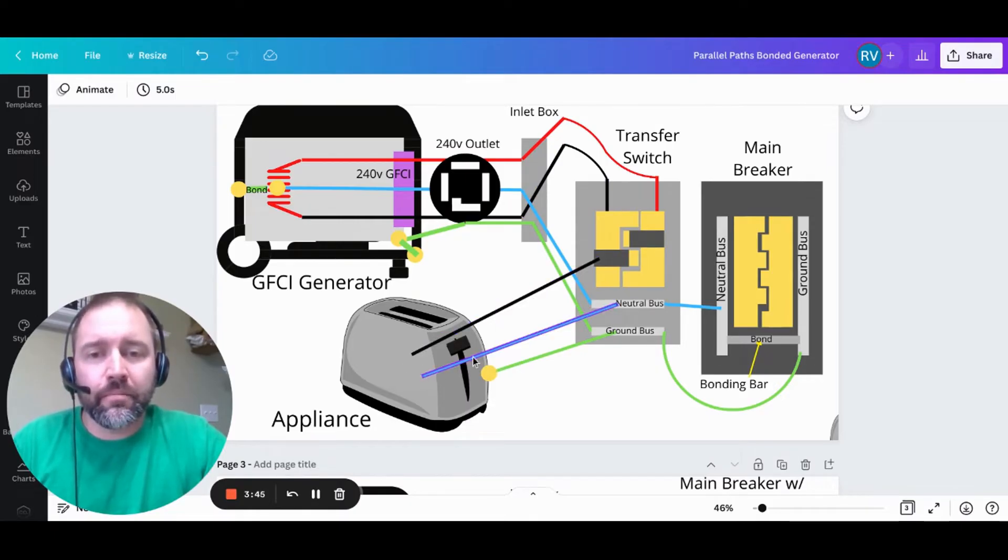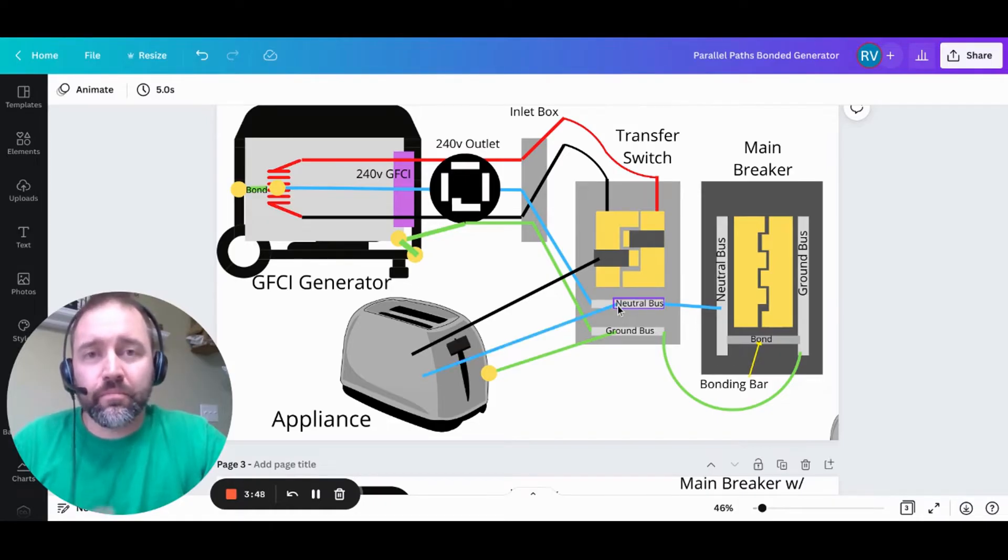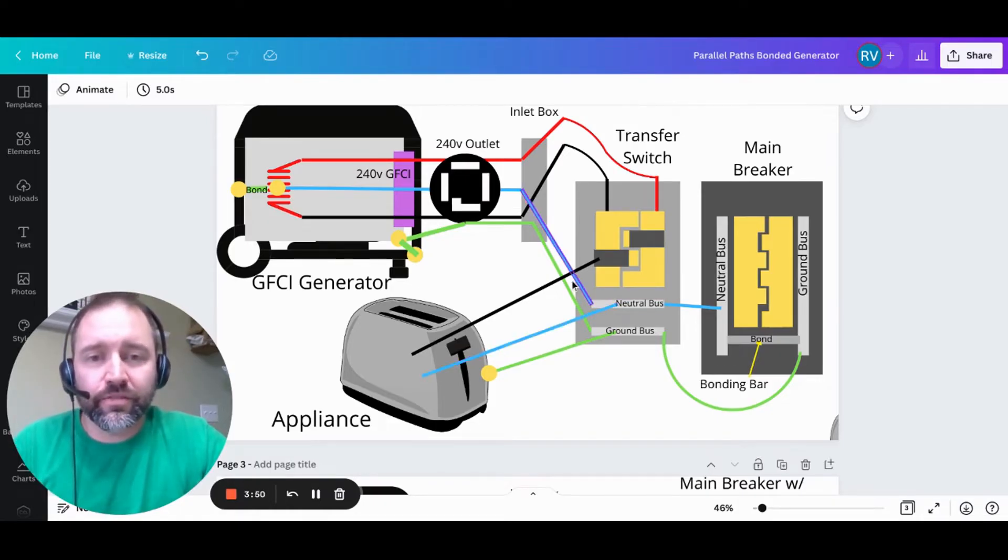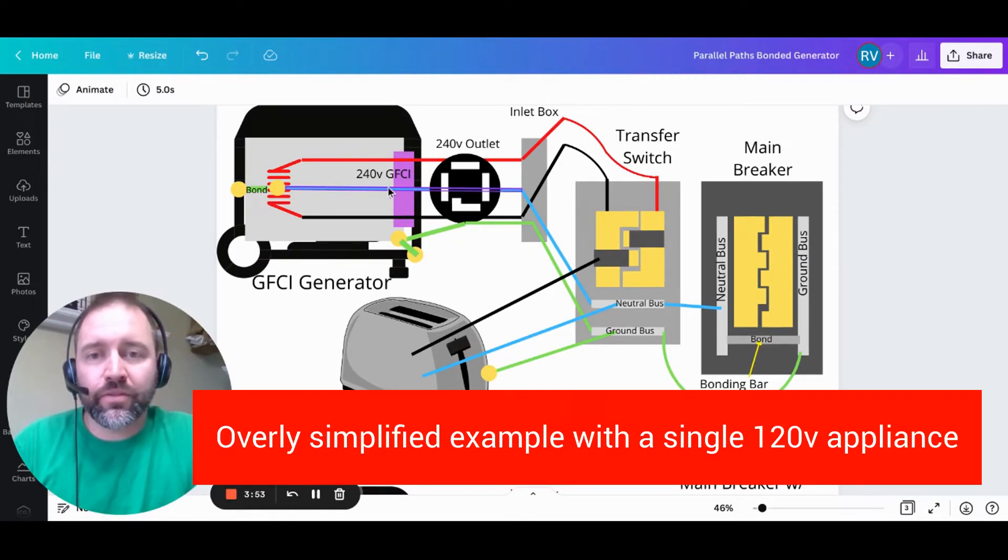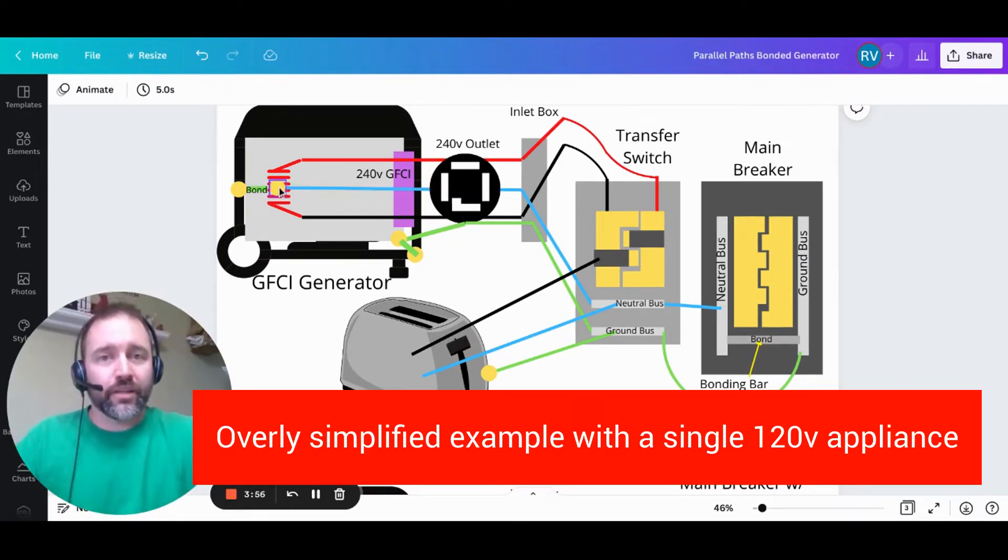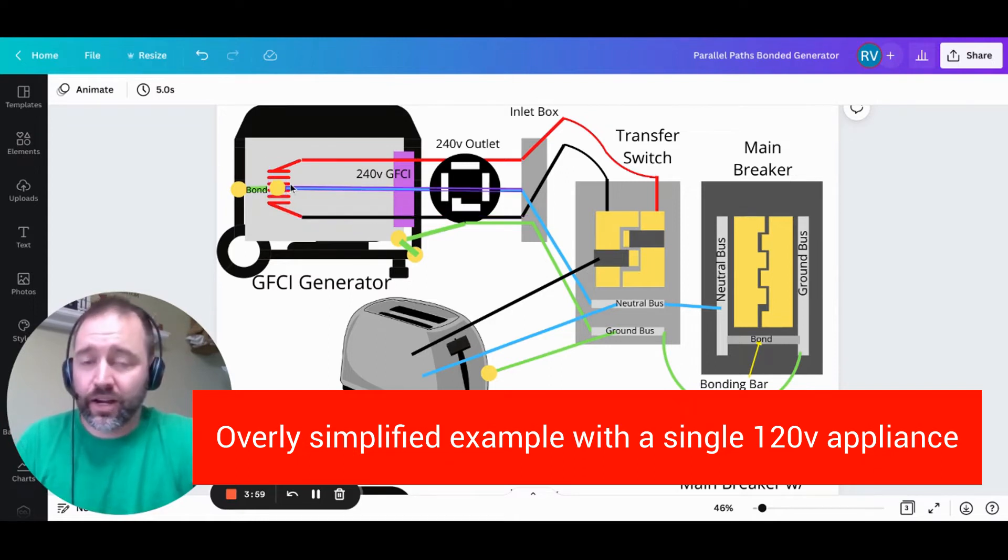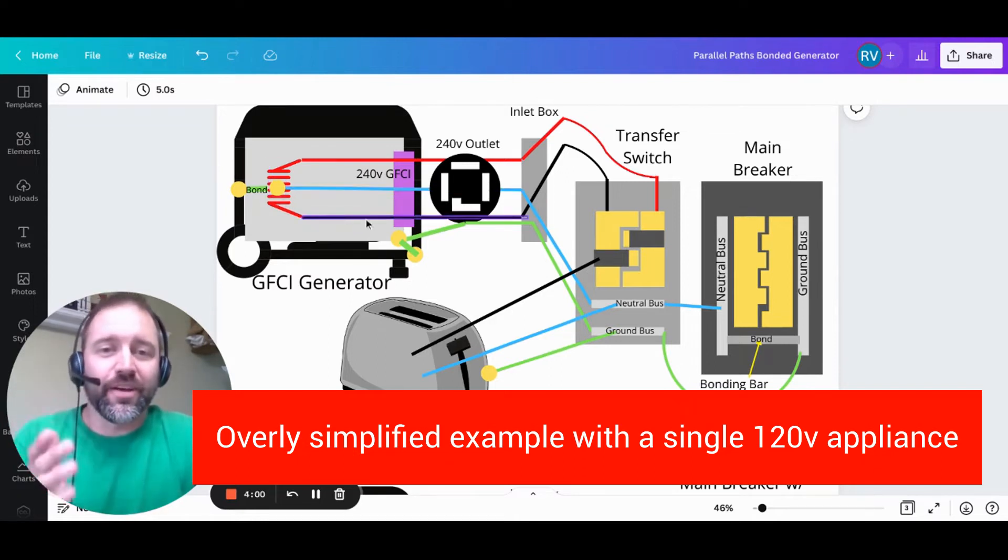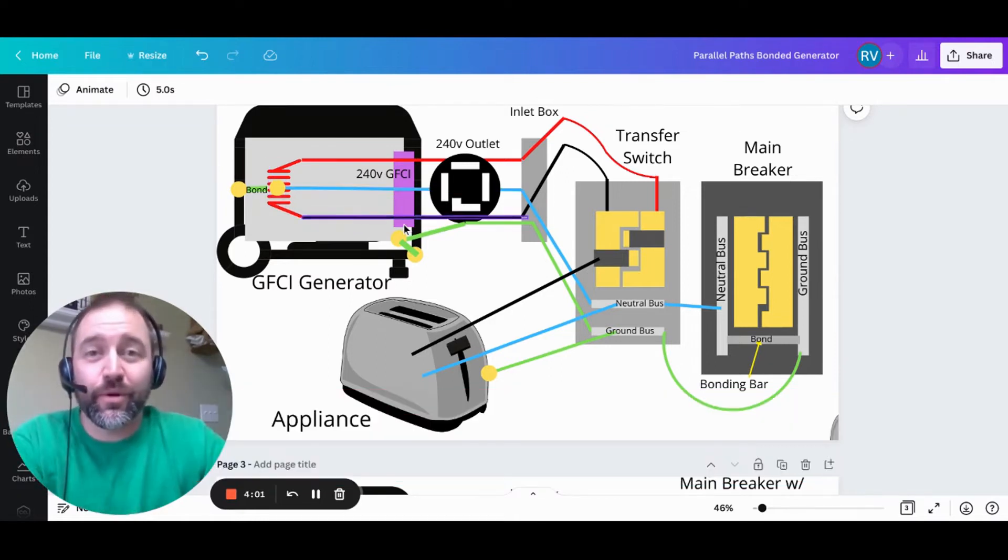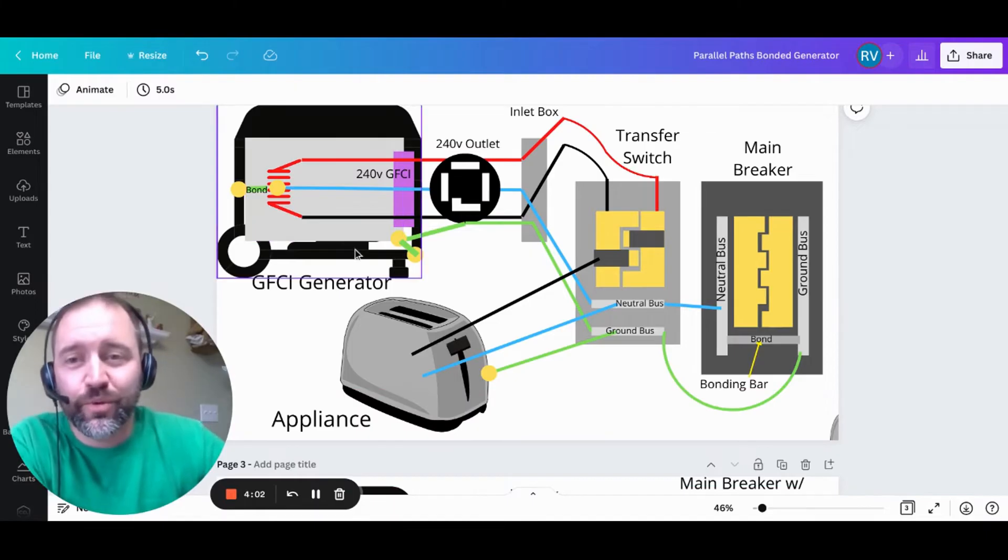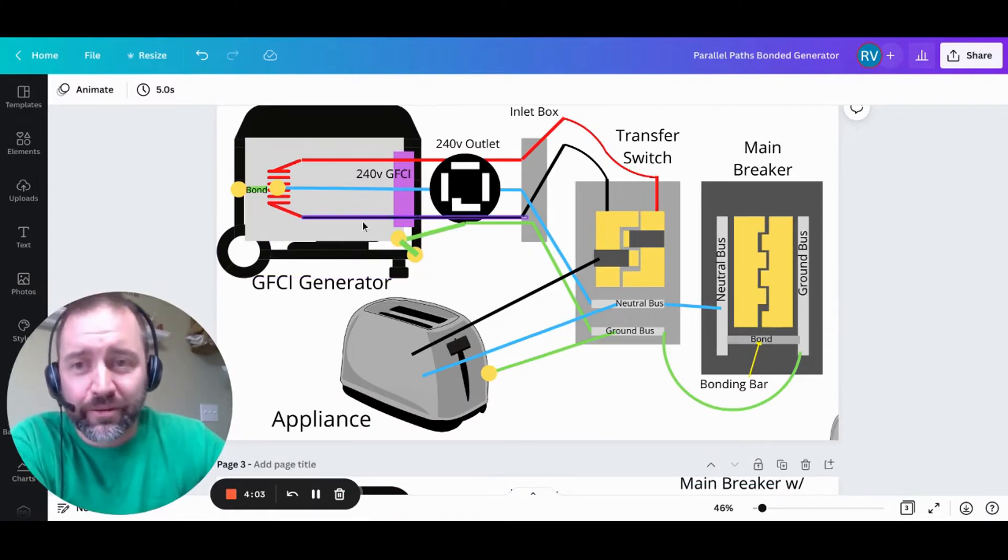It will then come back up the neutral, and in a perfect world, we would assume it's going to flow through this neutral, through the outlet, back through the GFCI, and complete the circuit since that's what it wants to do. It wants to leave and then come back. Well, in this case, this is where we're going to have some issues with everything tripping.